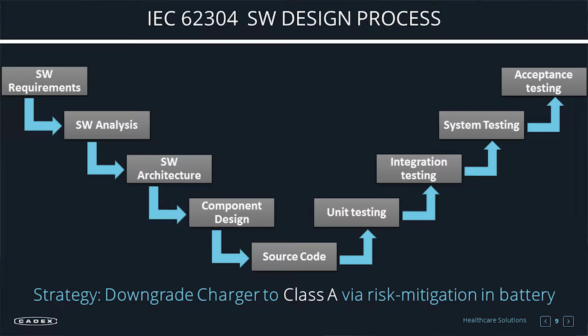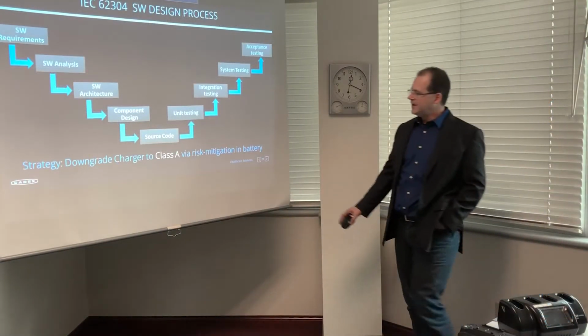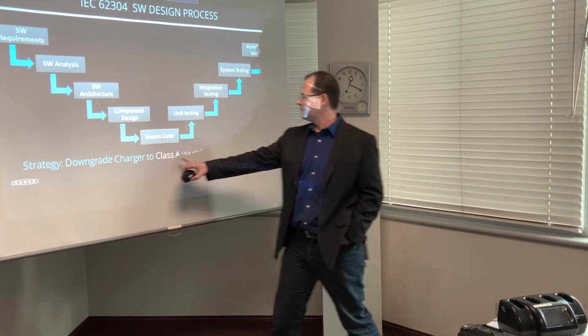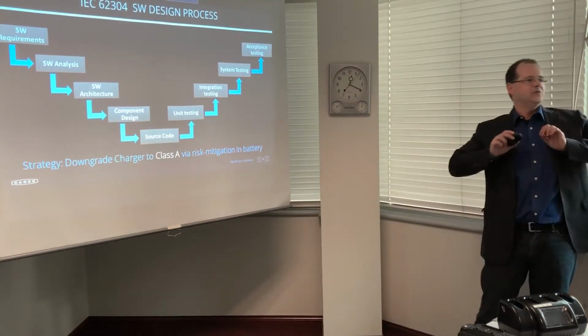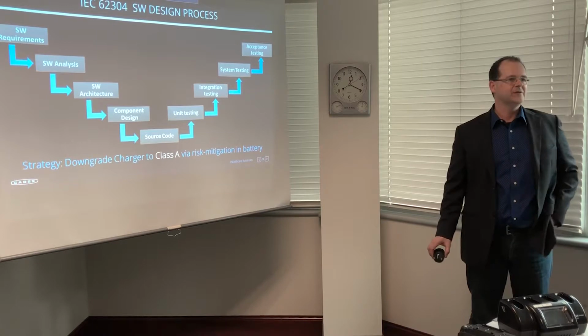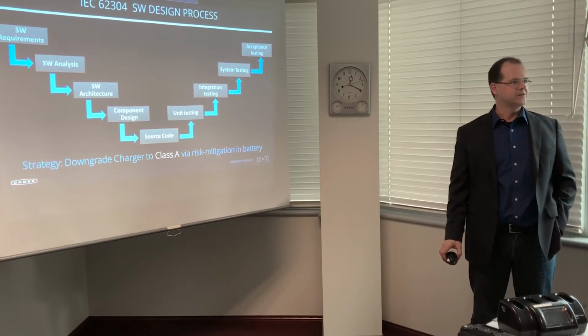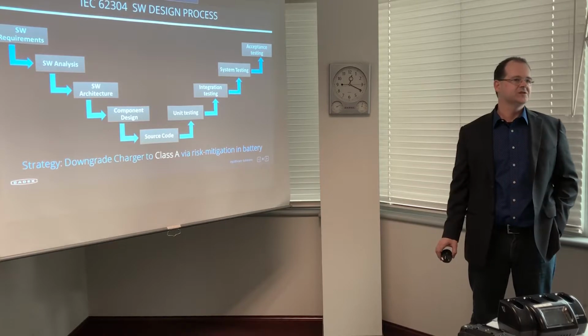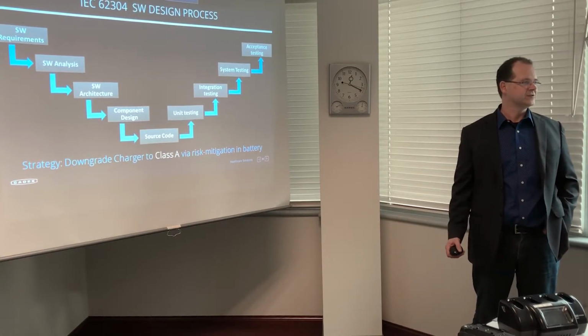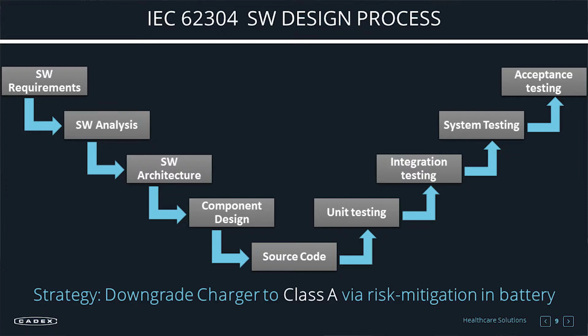So what that means for the strategy when you're doing a battery and charger system is that, if at all possible, when we're working in the front end with our medical device manufacturers, we want to convince them to downgrade the charger to a class A and move the risk mitigation efforts into the battery, where it can be done more with hardware and with systems that don't involve these huge levels of effort on the software development side in the charger, because the charger software is quite a bit more complex. So, just a little bit about the strategy when we implement the development process there.